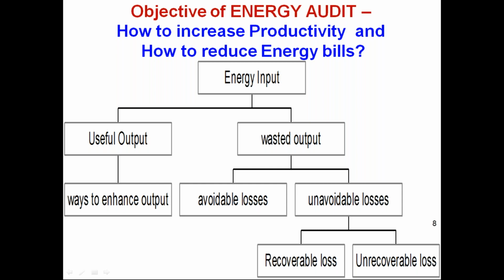If you are maintaining the motor well, we can maintain the same no load consumption that is given by the motor OEM. We cannot allow the industry to increase the no load power. It is not only on the motor, the same applies to the transformer also. A transformer will have avoidable loss and unavoidable loss. For the avoidable loss, reducing the kVA demand for the given transformer is more important.